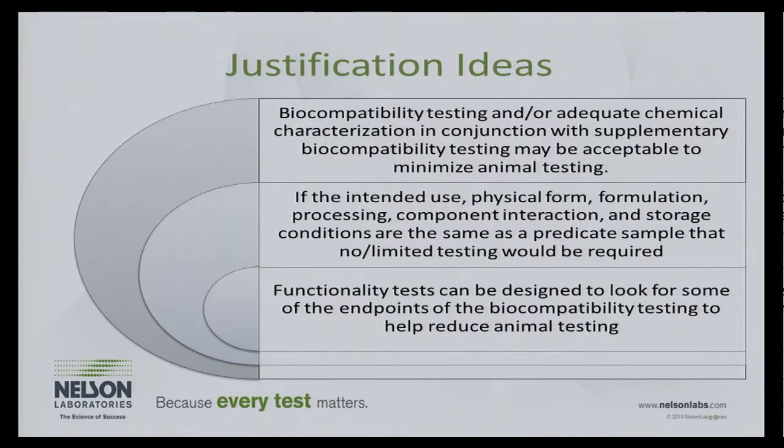So it gives you what the FDA looks for in justifying. For me, that's going to be hard to get for my competitor's product. But if you have your own product on the market that has a lot of these same endpoints, then we can use that to justify out of biocompatibility. And we've done so very successfully.